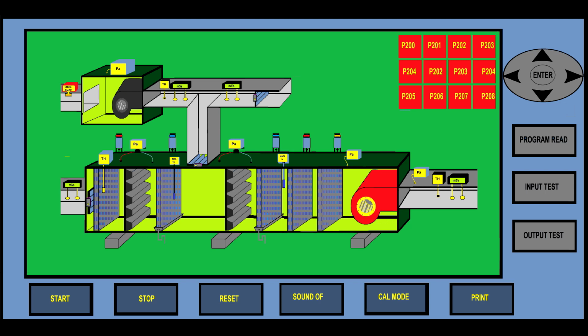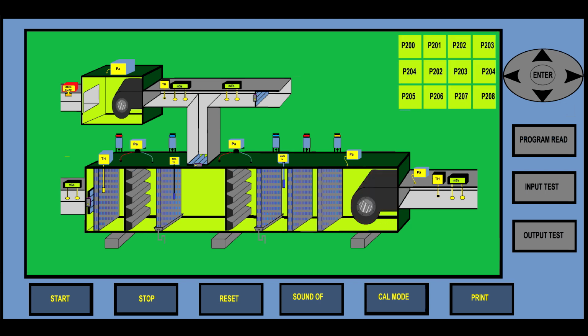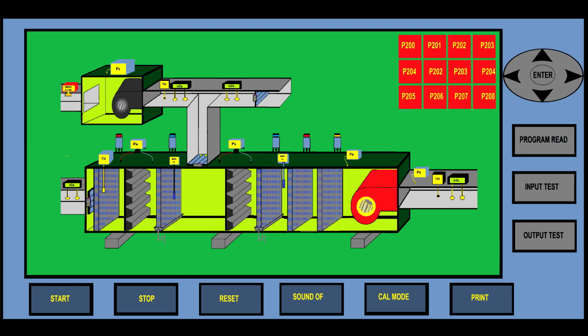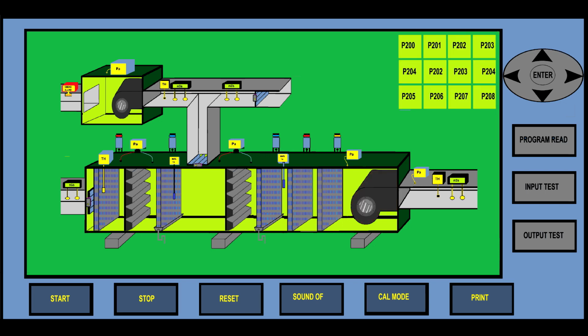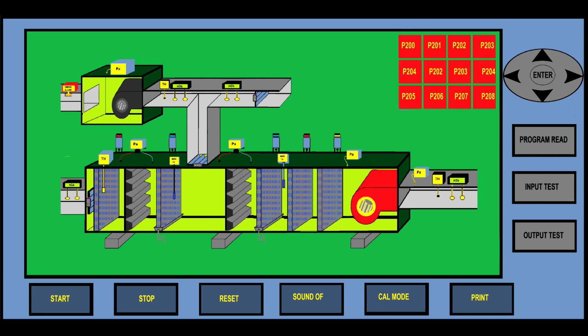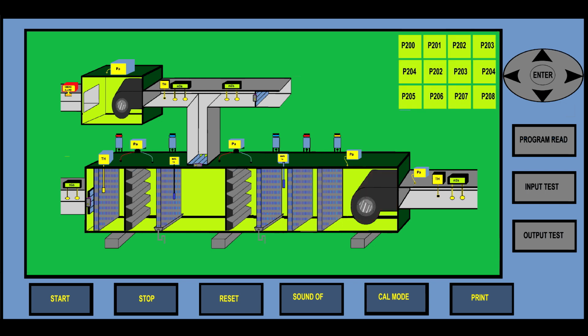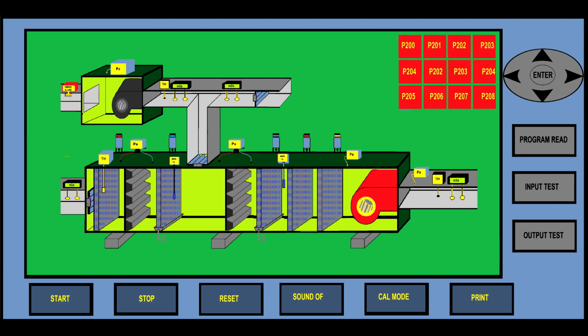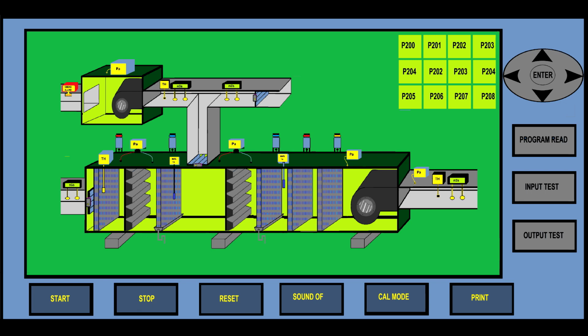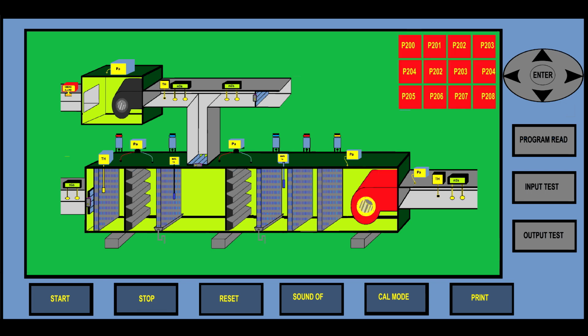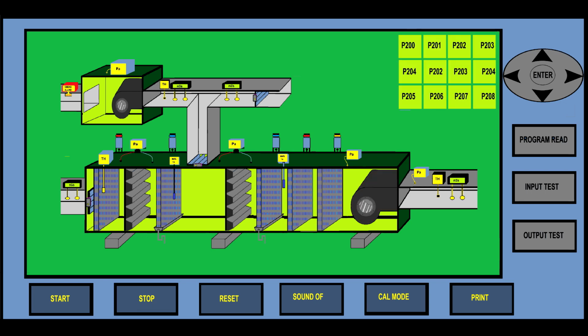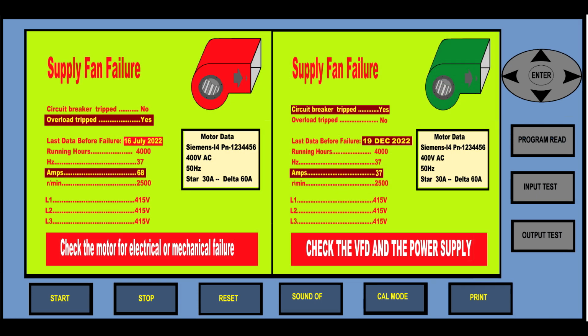Now, what you'll see here is a disastrous failure in which a technician didn't take action when the first motor failed. He just ignored it. And the second motor failed. Now you lost the entire airflow, the entire cluster is compromised. You see all the rooms are in red. You lost the pressure. That will lead to deviation and root cause analysis, which will probably lead to many other things, but not technical.